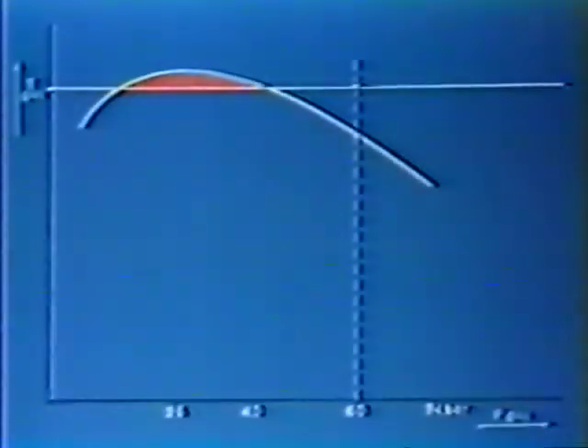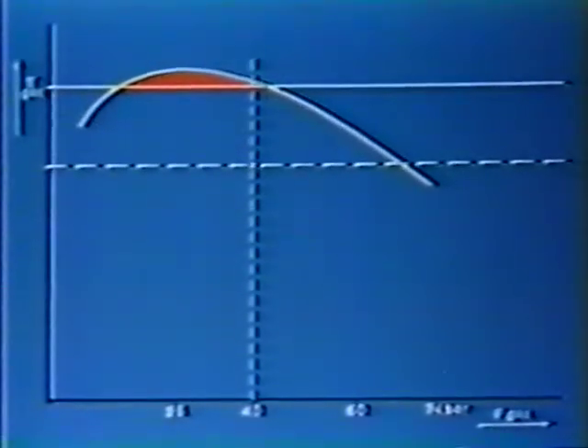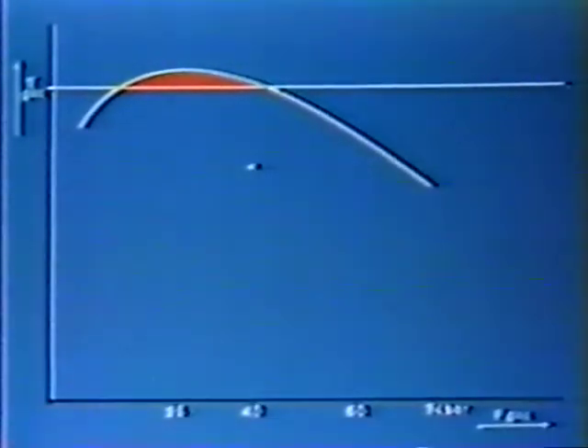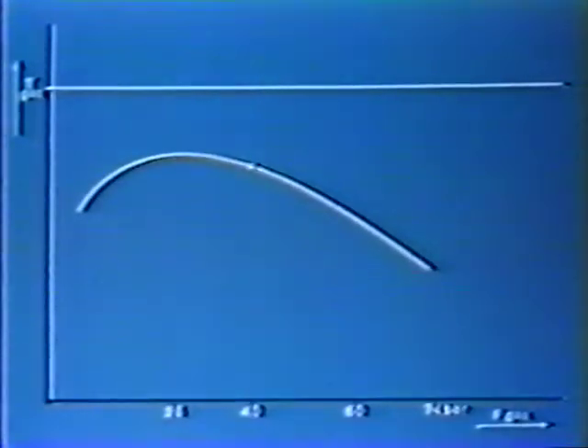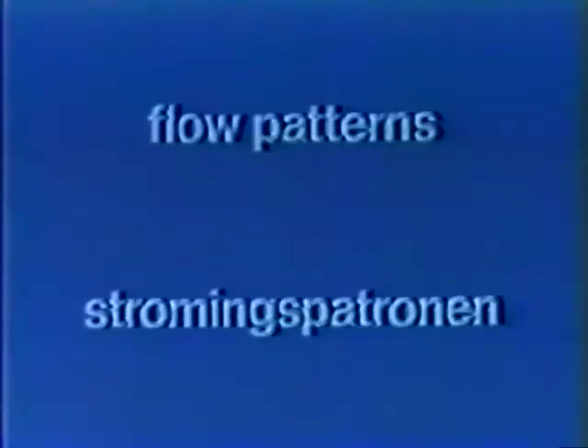What happens downstream of the station can be seen from the course of the condensation curve. Expansion to 40 bar causes the gas temperature to drop. This in turn gives rise to condensate in the form of a mist. When the condensate is separated from the gas stream, the dew point drops to far below the ground temperature at pipeline depth. This drying by expansion at the measuring and regulating stations is so effective that hardly any further condensate is likely to be formed further down the network.